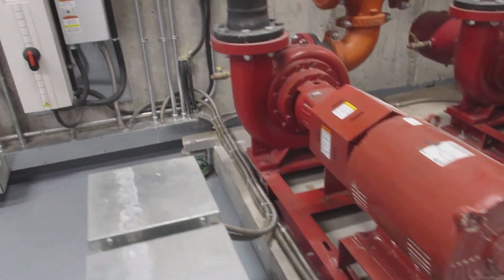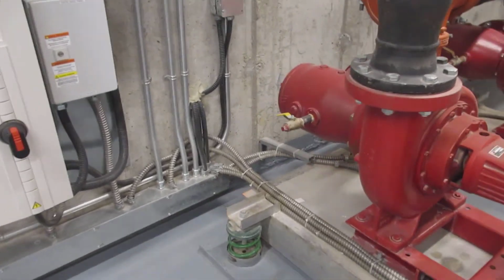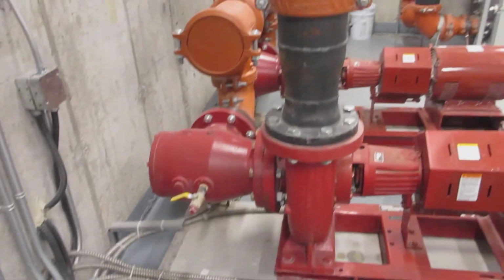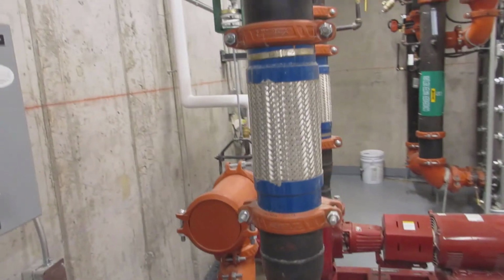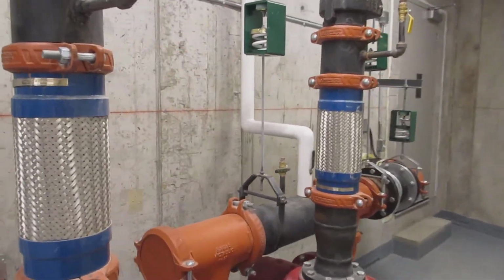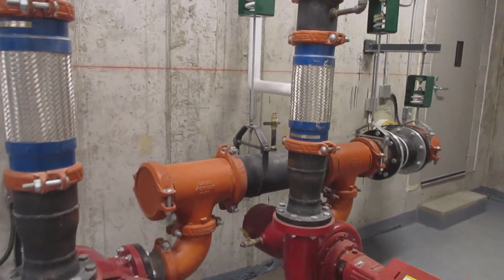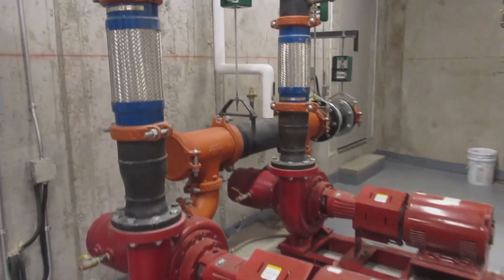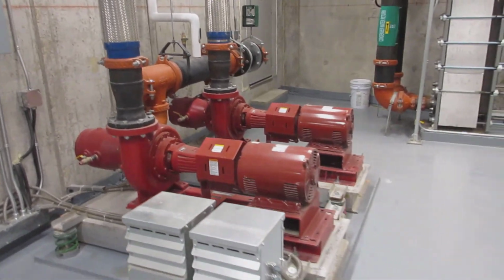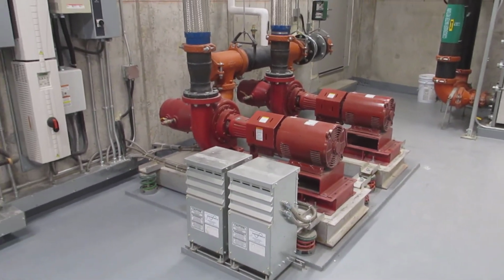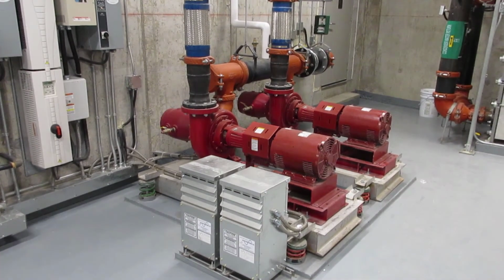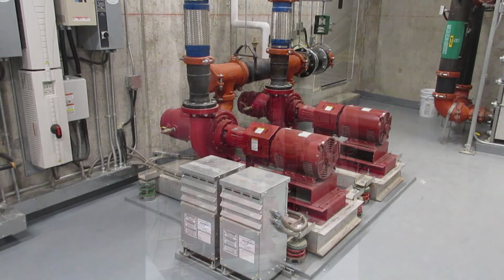Over on the pump end, we can see a bunch of flexible conduits attached to the wall. Looking up, we see the flexible metal hose connections on the discharge pipes and spring hangers on the inlet pipe, which allow the whole system to move. Check out our other videos on these products. So, what do you think of these? Are they close enough, or are there things the contractor needs to fix? Again, hold on to your answers, and let's go look at the third set of pumps, the chilled water pumps.